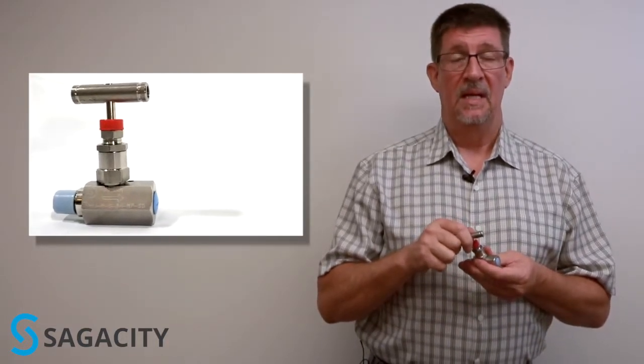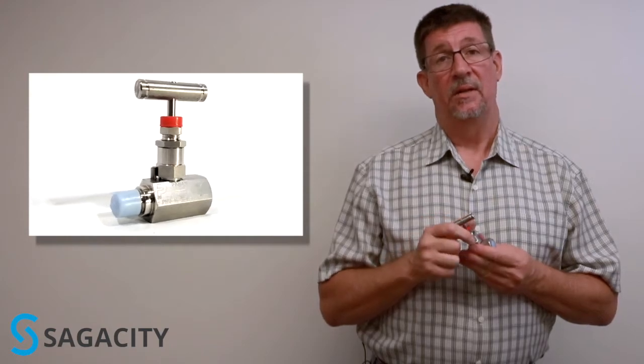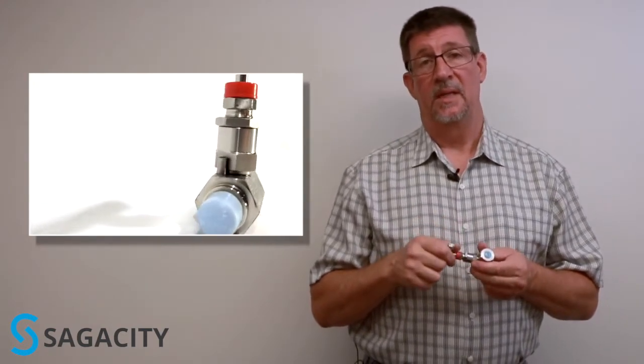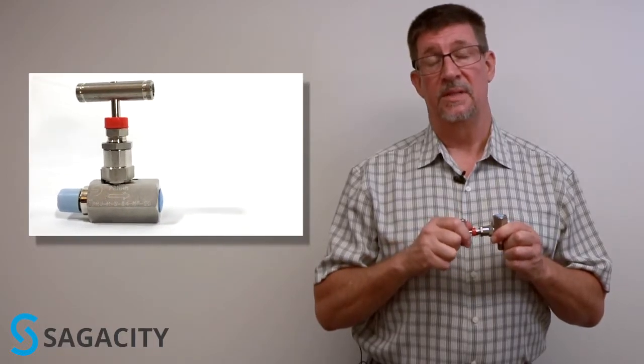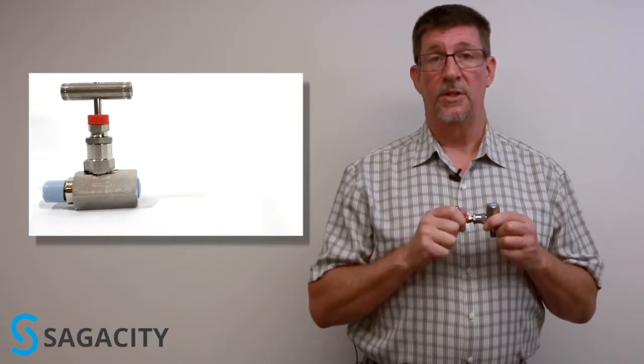Finally, handle type. If you see a T-handle, it's a good indication that this valve is being used as a root valve or a simple on-off valve in an application, say, as a root valve to a pressure gauge.